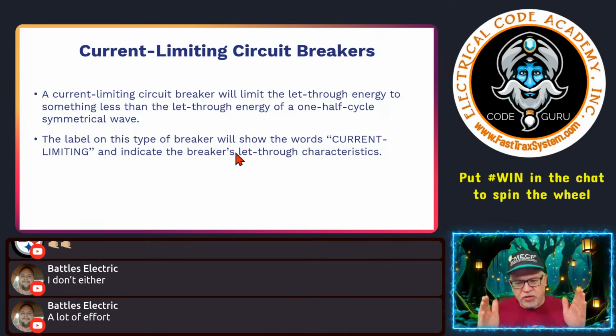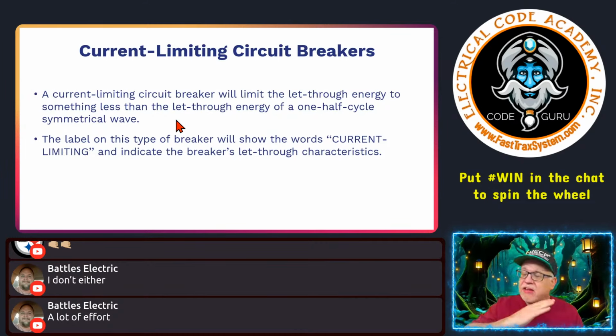So you have one full cycle, 60 hertz, one full cycle, changes directions. Now, one full wave, then you have 1/2 of a full cycle. So it's half of a full cycle operation, and that is its current limiting. That means it's going to shut off very quickly, in half of one full cycle. So it's current limiting. It's not going to let the energy run a full cycle. It's going to stop it at 1/2 cycle of the symmetrical wave, the sinusoidal waveform.